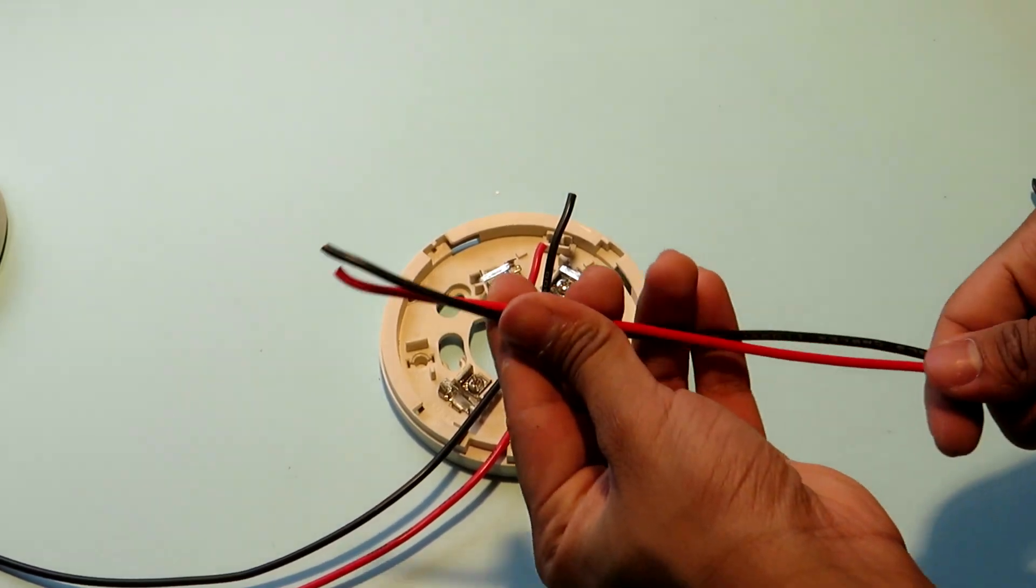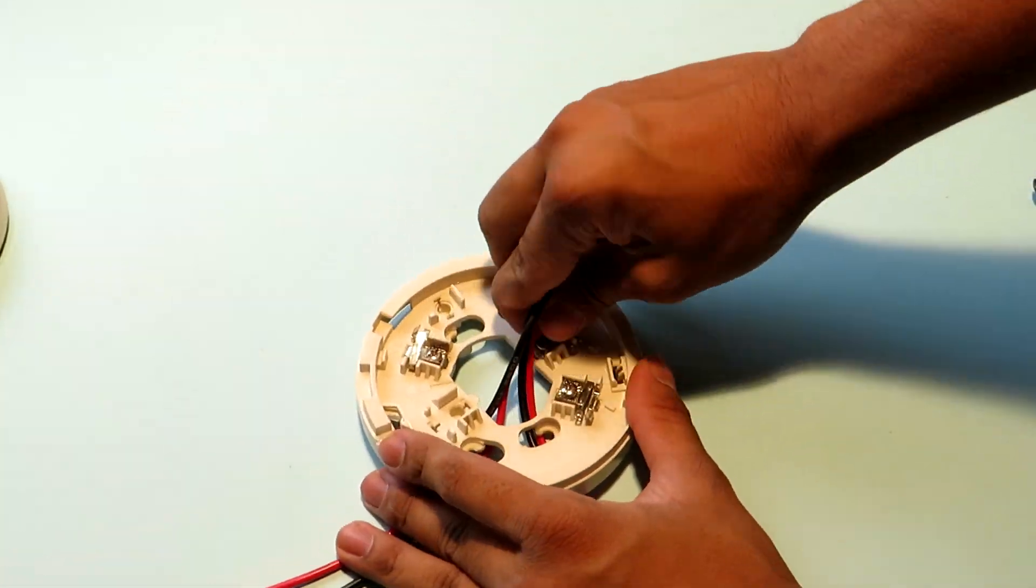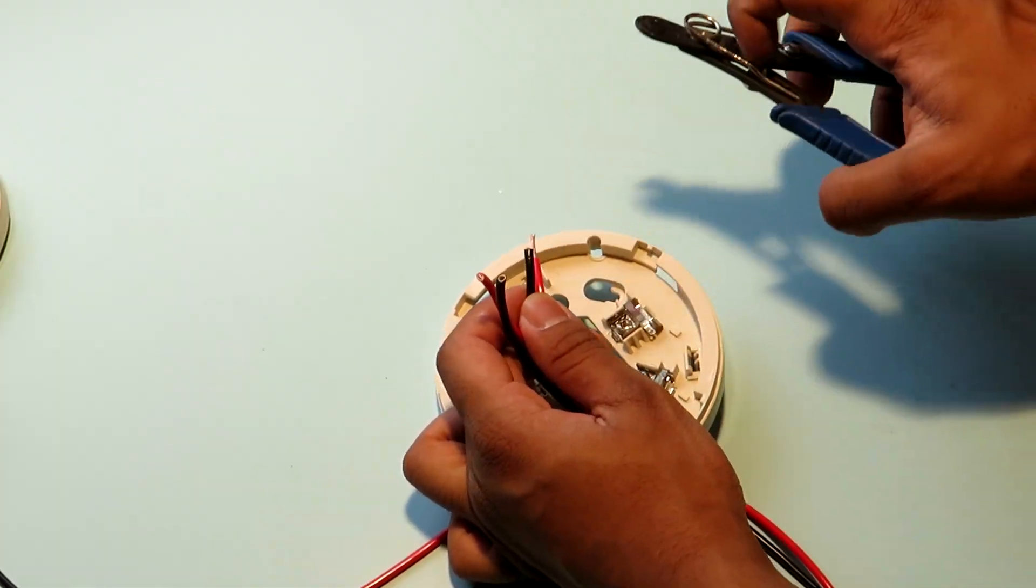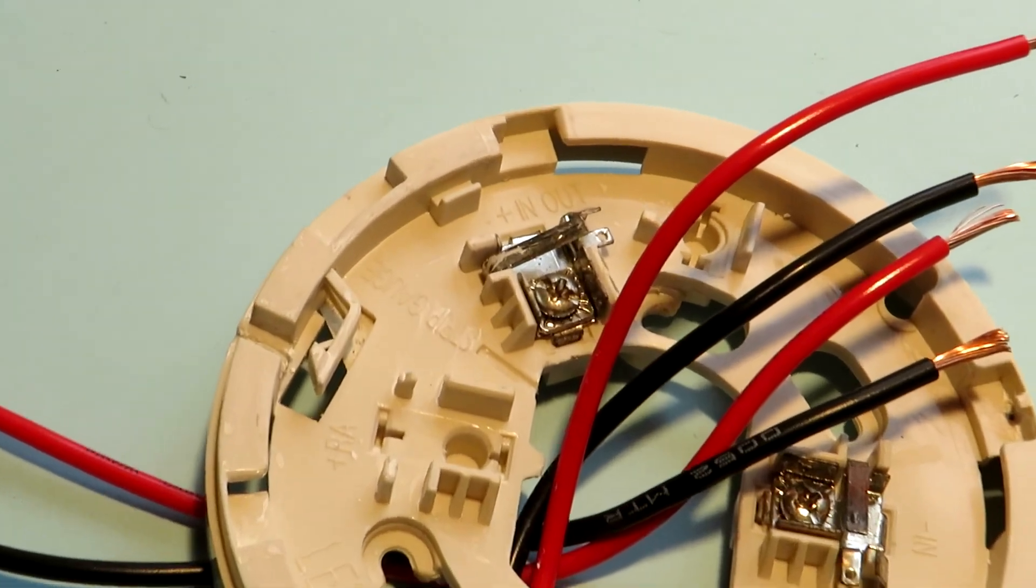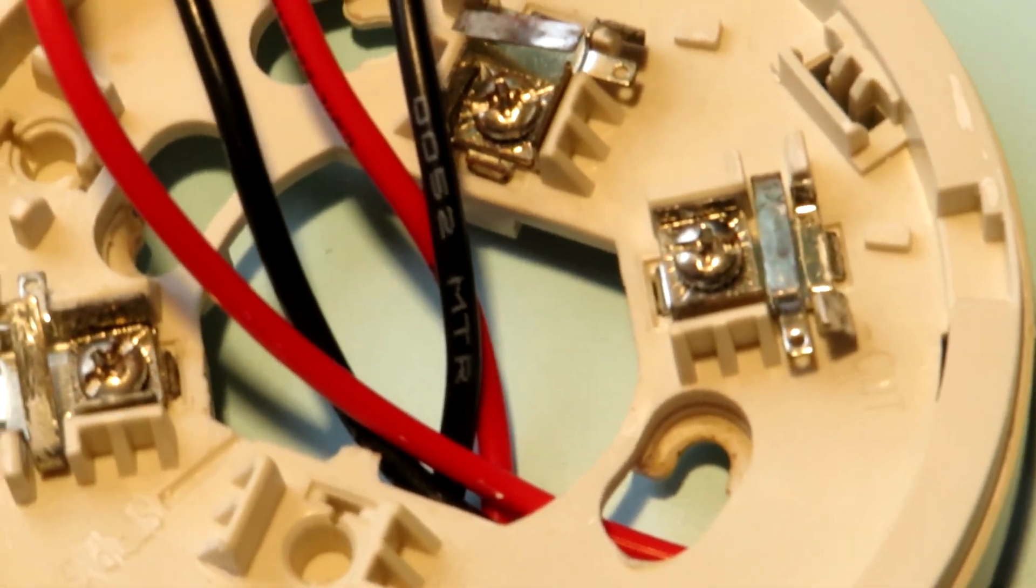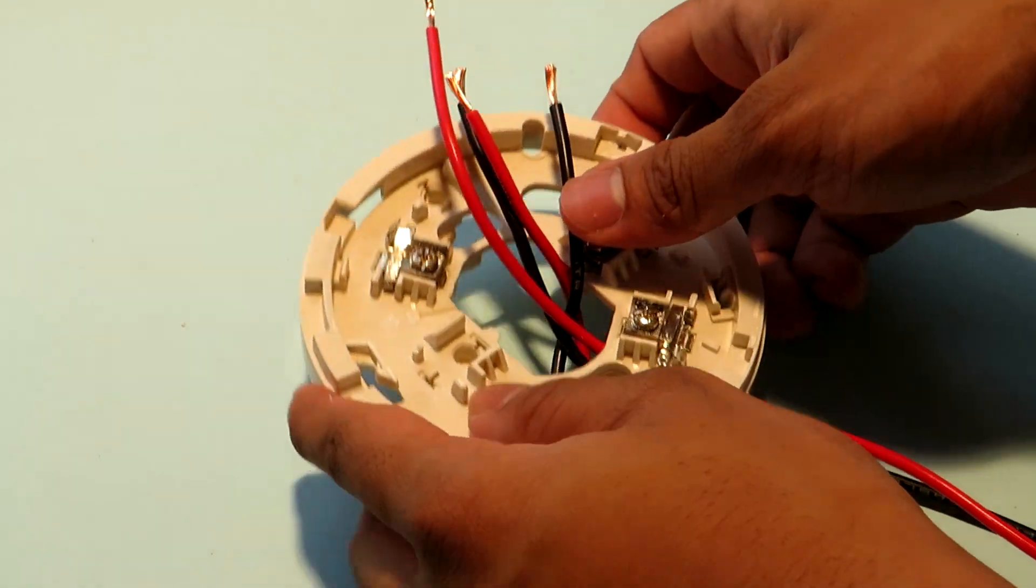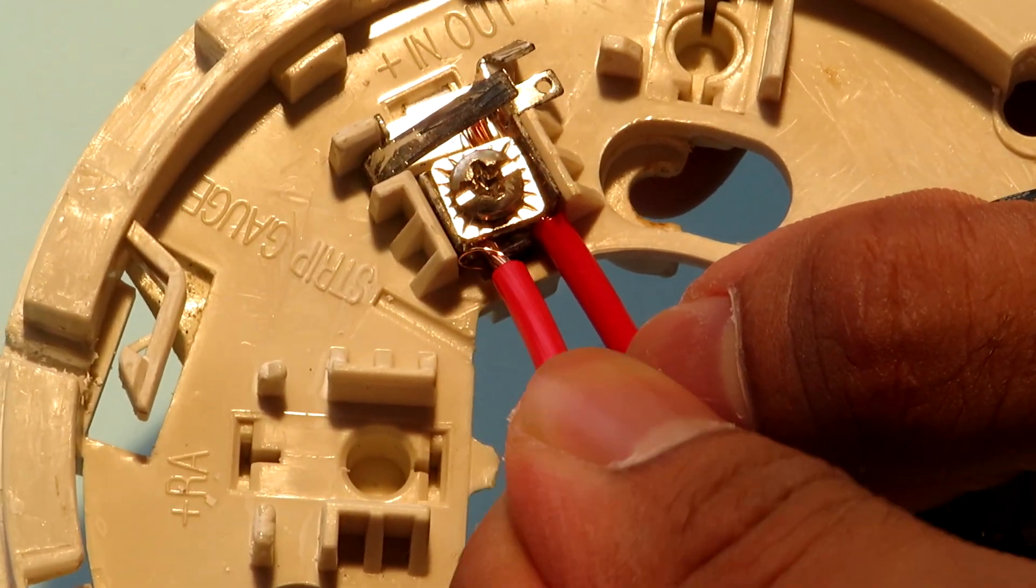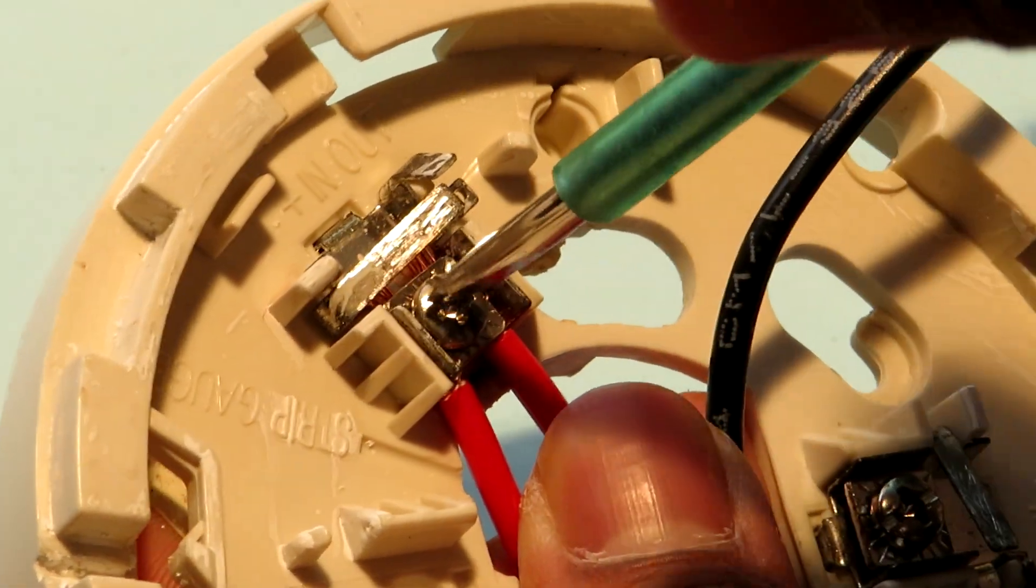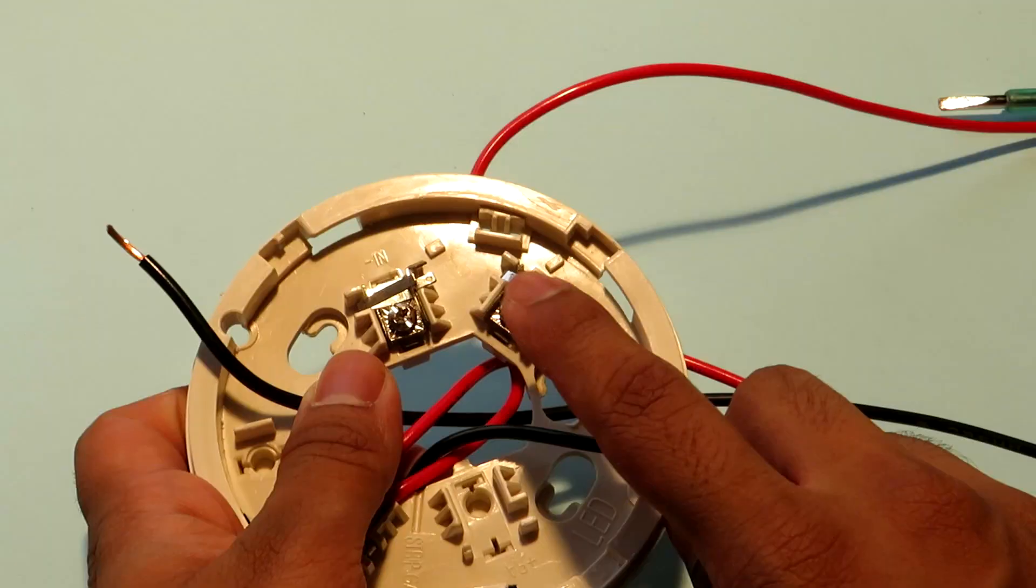Now coming to the connections. So this is our incoming cable from the fire alarm control panel. So first we'll pass all the cables from the back side into the base unit and then skin them. Now we are going to make the connections as per the schematic which I showed you earlier. As far as the positive wire is concerned they both go to the same terminal which is labeled positive in out. So now we have connected our positive wire successfully.